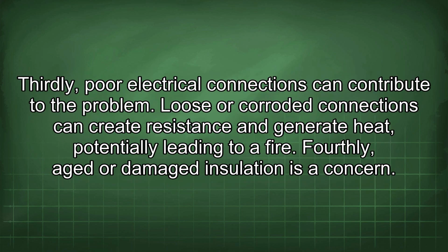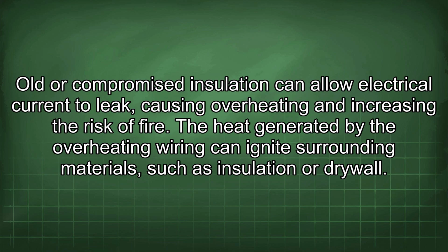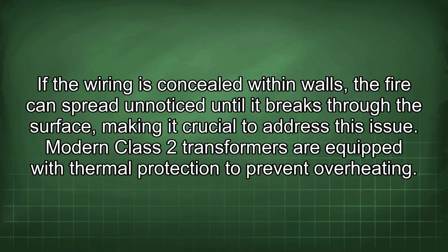Thirdly, poor electrical connections can contribute to the problem. Loose or corroded connections can create resistance and generate heat, potentially leading to a fire. Fourthly, aged or damaged insulation is a concern. Old or compromised insulation can allow electrical current to leak, causing overheating and increasing the risk of fire. The heat generated by the overheating wiring can ignite surrounding materials, such as insulation or drywall. If the wiring is concealed within walls, the fire can spread unnoticed until it breaks through the surface, making it crucial to address this issue.